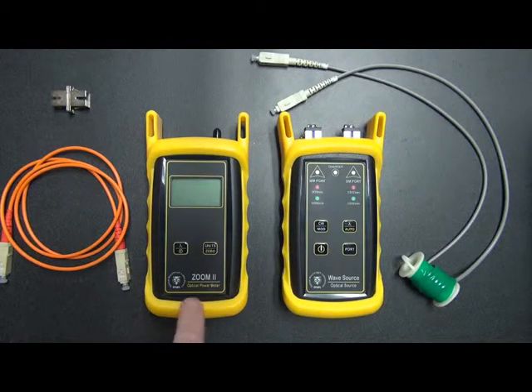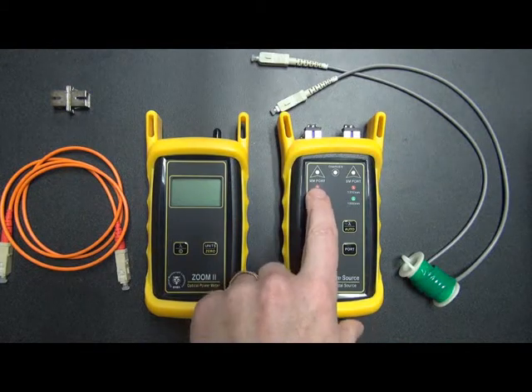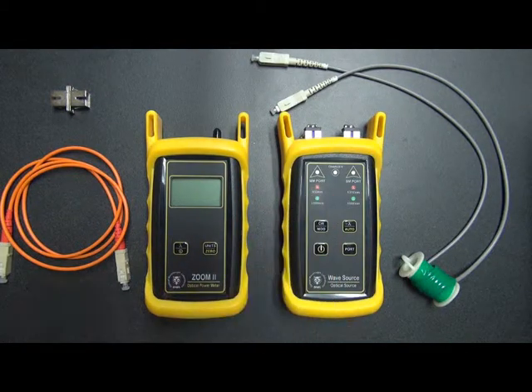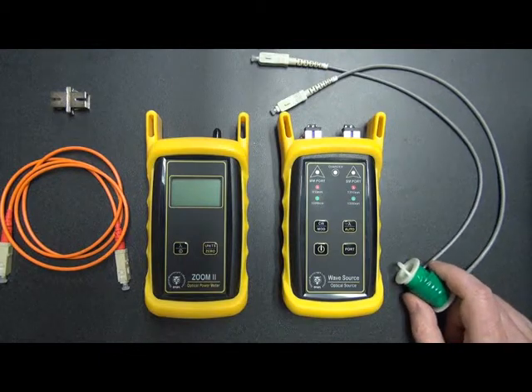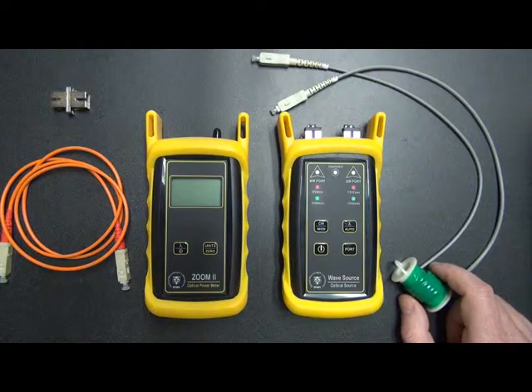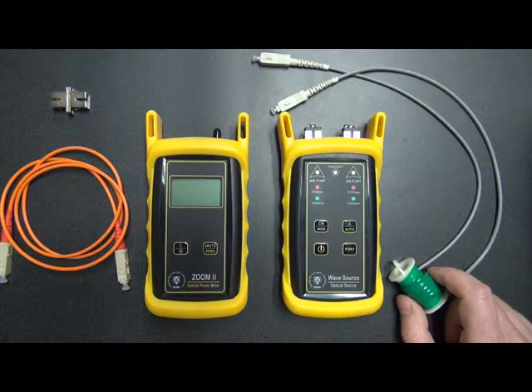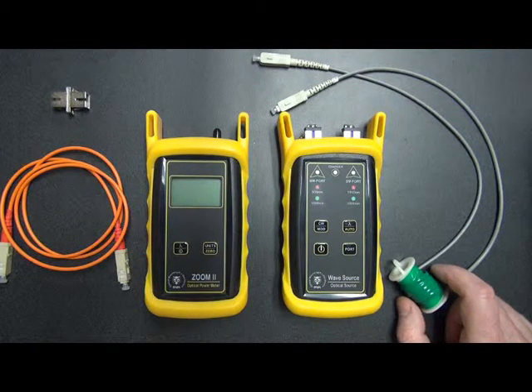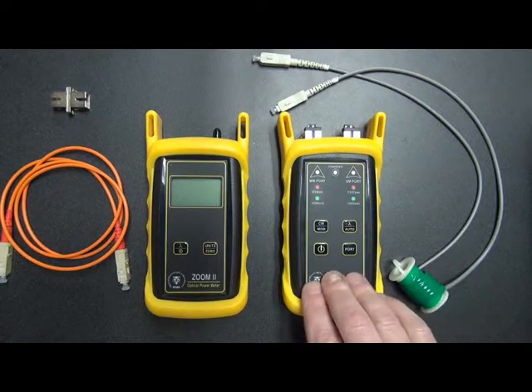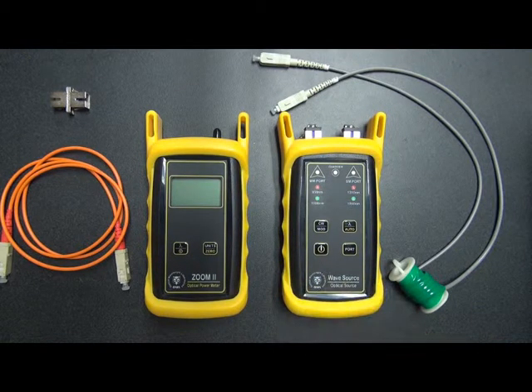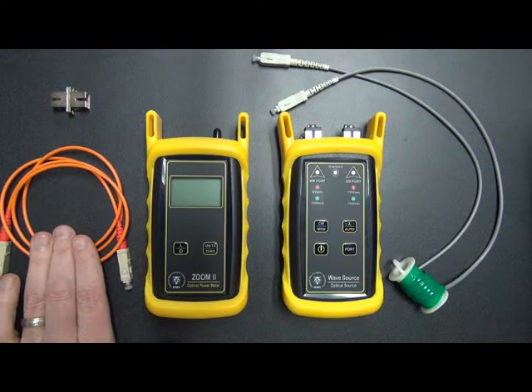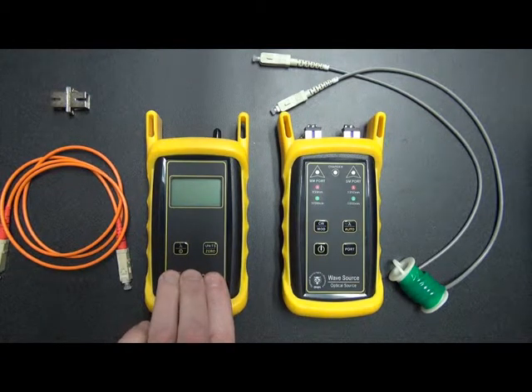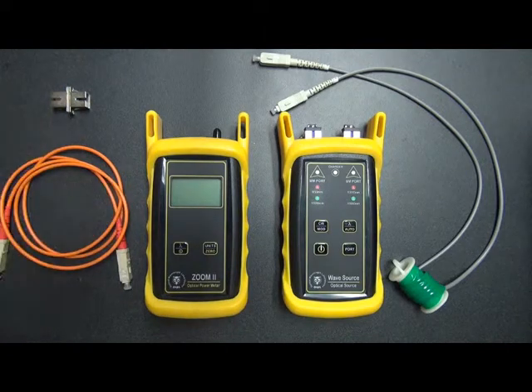In this procedure, we will be using a Zoom 2 optical power meter and the multimode port on a WaveSource light source. Now you'll notice that there are two patch cables and one mating sleeve used for this procedure. Because this is multimode fiber, we're wrapping one of these reference cables around a mandrel per testing standards. This cable is used to zero out the equipment and also to connect the WaveSource to the link under test. The second cable is used to connect the Zoom to the link under test.